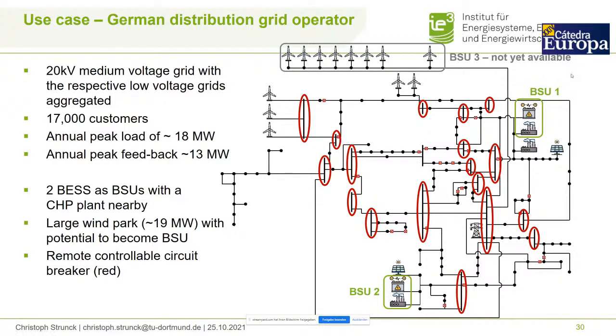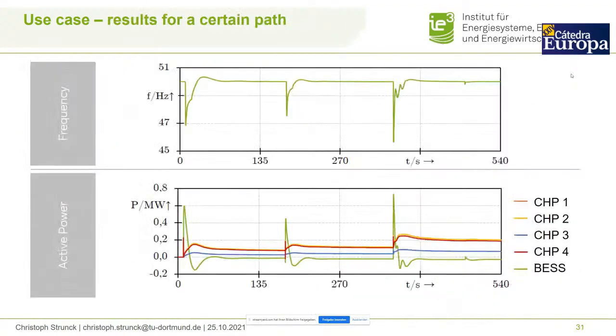With that, we started some investigations and simulated the grid with dynamic simulations. We tried to model the wind farms, PV plants, and CHP plants in the grid as realistically as possible to get a grid restoration plan. Here you see some results for the grid restoration process. You see that a frequency below 46 hertz can occur during a grid restoration in the distribution grid, because we don't have enough inertia to avoid that.